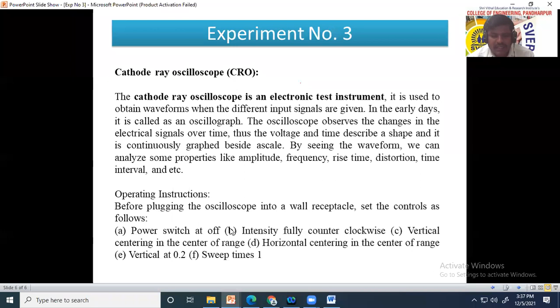Okay, so there are some operating instructions. Before plugging the oscilloscope into a wall receptacle, set the controls as follows. First, the power switch at off position. Intensity fully counterclockwise. Then vertical centering in the center of range. Then horizontal centering in the center of range. Vertical at 0.2 and the sweep time at 1. So these are some of the operating instructions of the cathode ray oscilloscope.